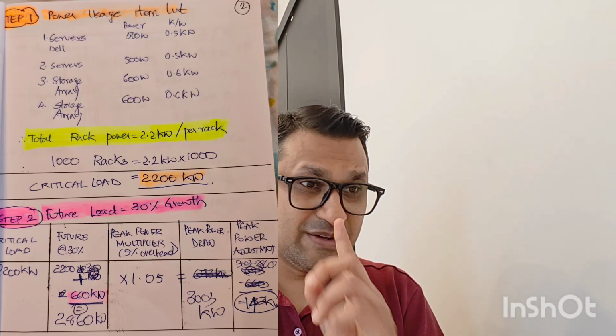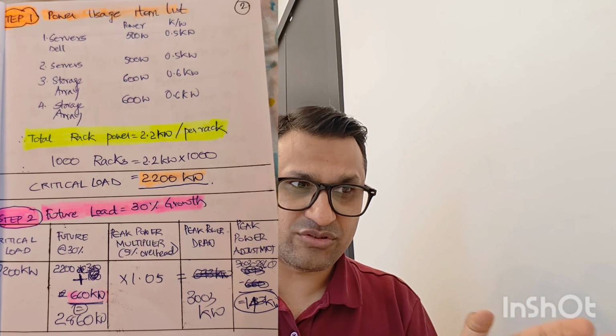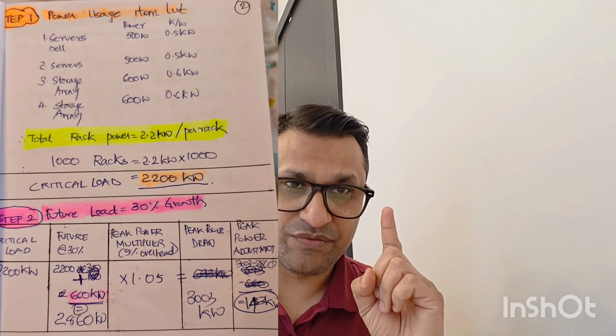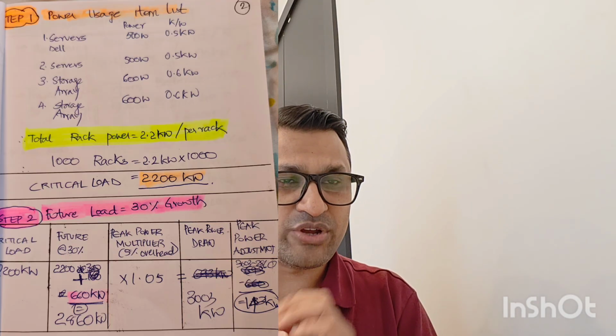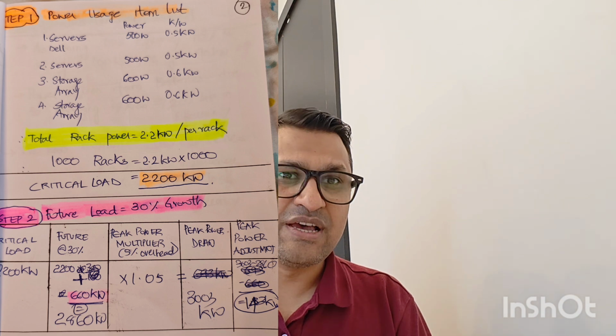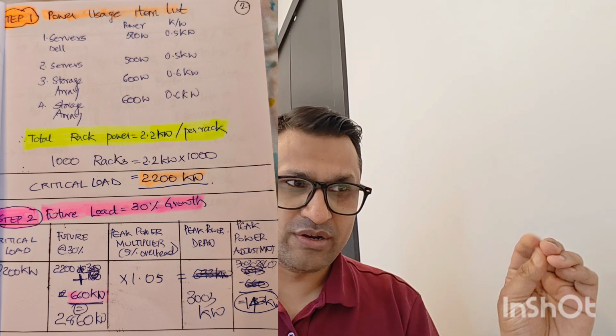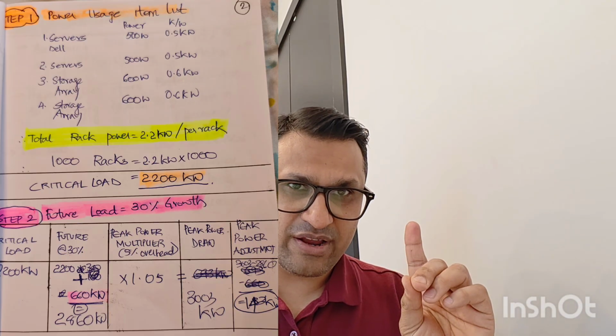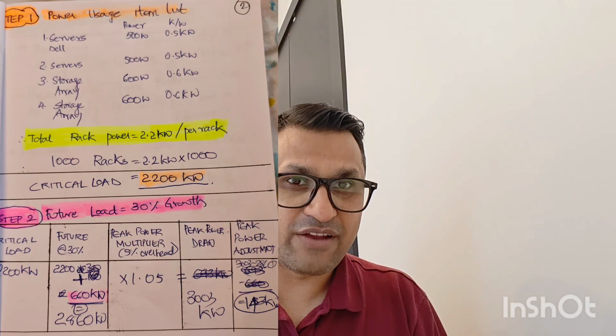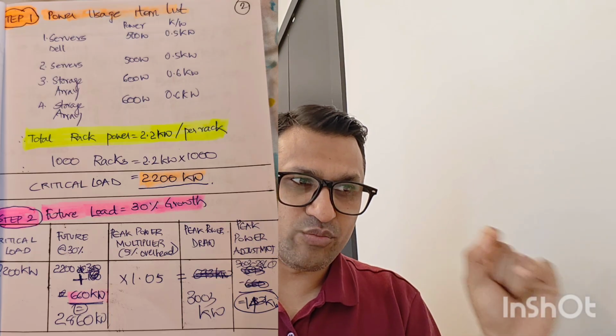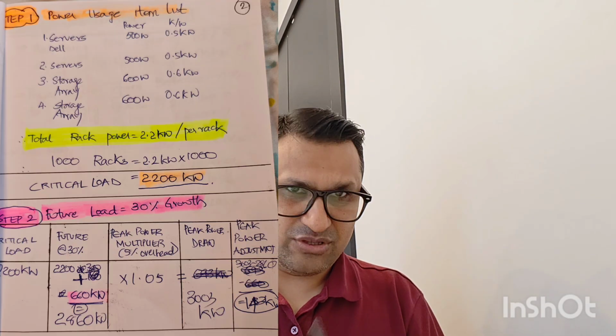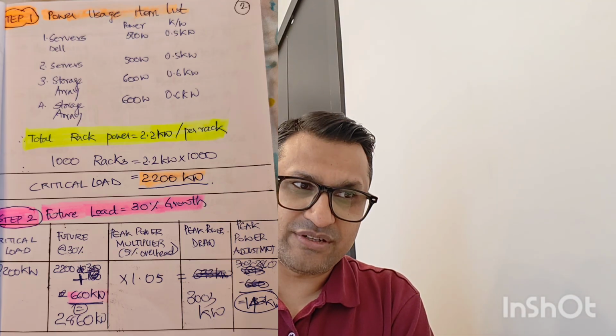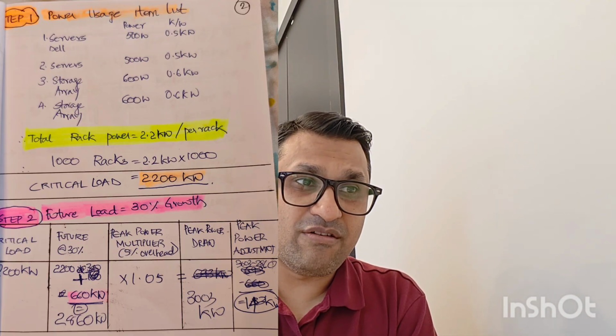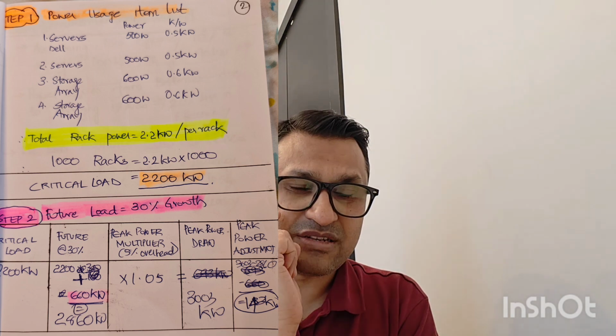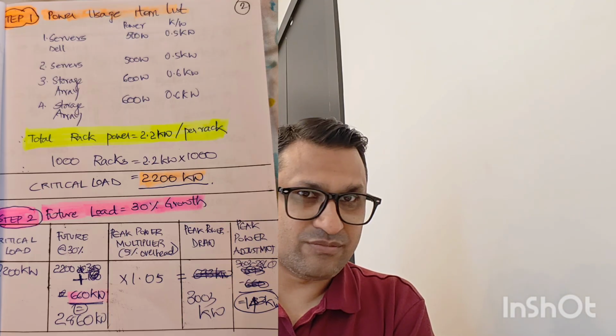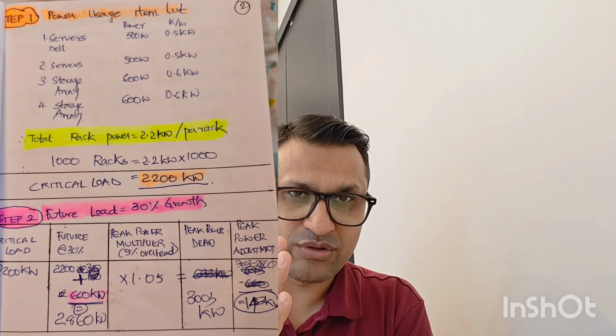So if you're considering 1,000 racks for this large scale data center, 100,000 square feet, let's consider the power calculations for one rack first. In one rack, if you're putting in two Dell servers and two storage arrays, having a power rating of 0.5 kilowatt and 0.6 kilowatt, then for one rack, for design purposes, it is 2.2 kilowatt per rack. And if you have 1,000 racks, now you have 1,000 times 2.2, which is 2,200 kilowatt. That's the critical load. That's the main load for this 100,000 square feet data center. That was step one: power usage for one rack times the number of racks initially proposed. 1,000 racks, one rack is 2.2 kilowatt, 2,200 kilowatt.